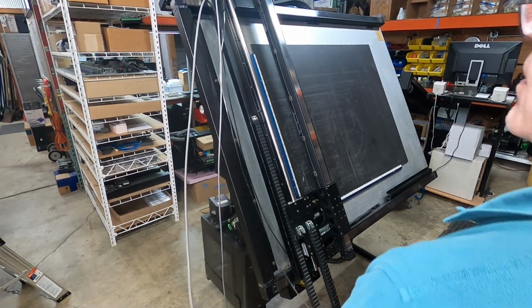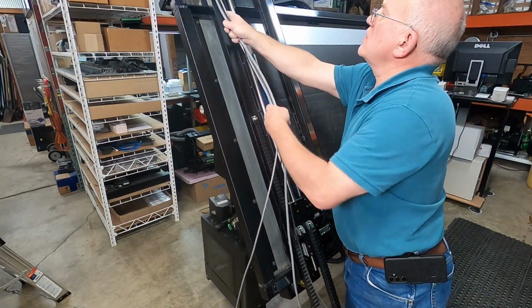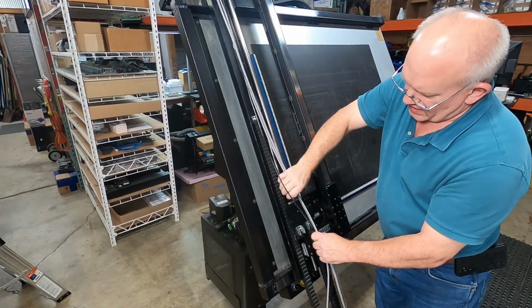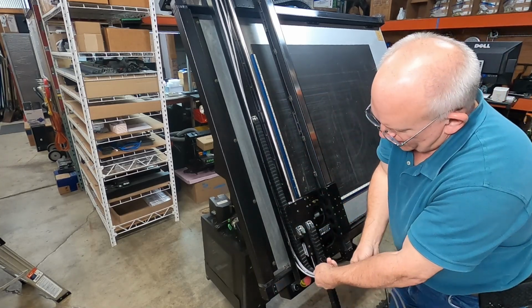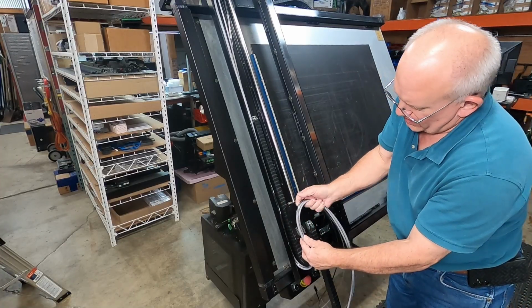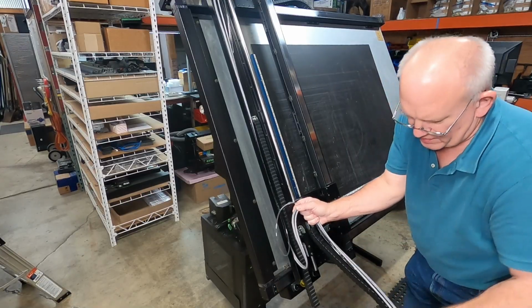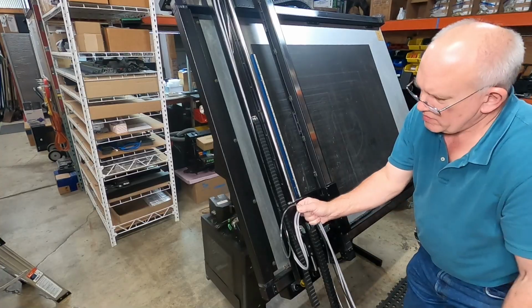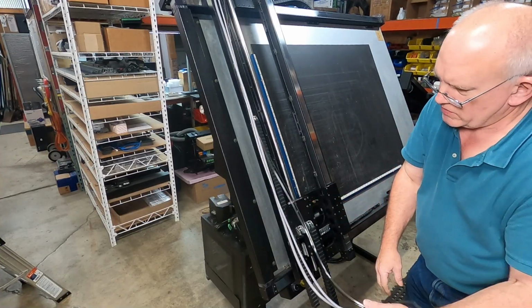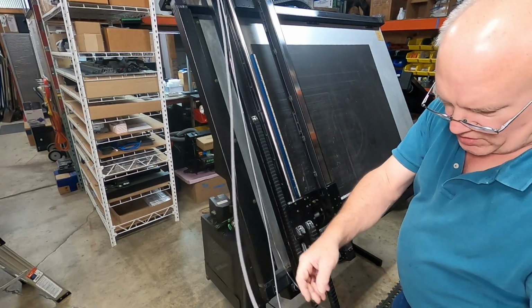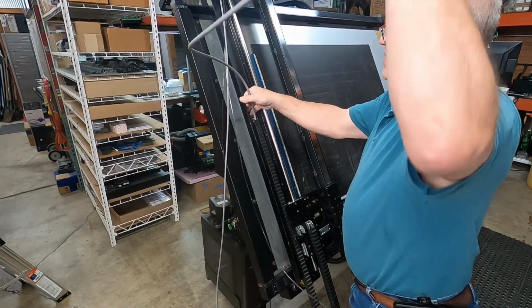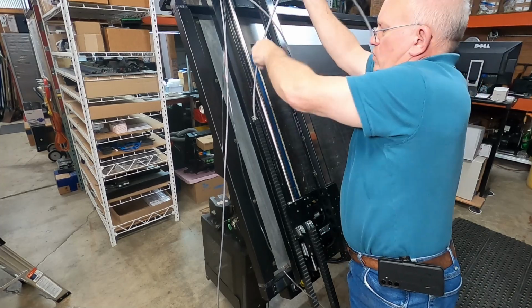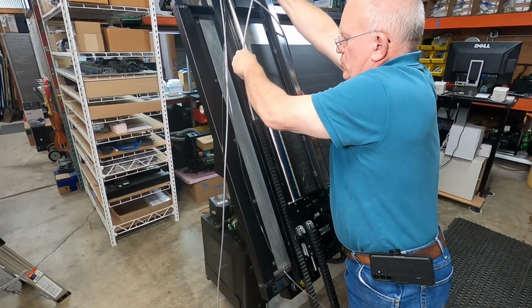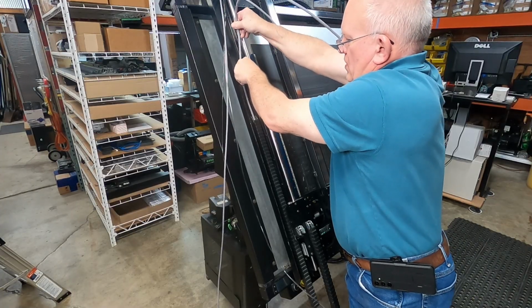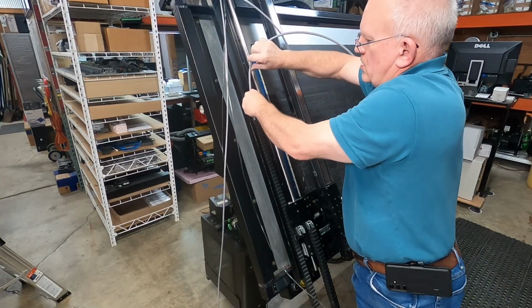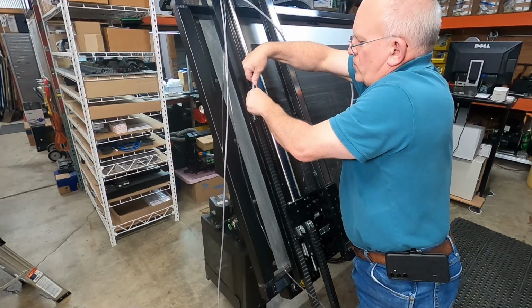These wires here have to go under this cover. They have to go down through this cable track right here. They have to wrap back up like here, bend around, and then go through this cable track here. So there's got to be enough wire before you start doing this, to reach that far. So the first thing I'm going to do is take the 12-conductor wire and stick it down through this cable track. You've got to wiggle it and twist it and push and pull and start and stop. Sometimes it goes easy, sometimes it just wants to fight.